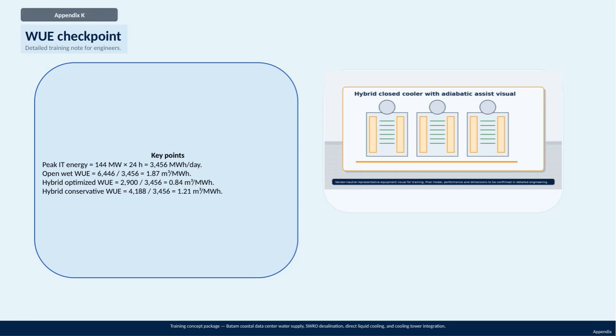This slide presents the key points from Appendix K, focusing on the Water Usage Effectiveness, or WUE, checkpoint for the Batam Coastal Data Center. The detailed training notes here are designed specifically for engineers and cover several important concepts, including water supply management, SWRO desalination, direct liquid cooling, and cooling tower integration. One critical figure to note is the peak IT energy consumption, which is 144 megawatts running continuously for 24 hours, totaling 3,456 megawatt hours per day.